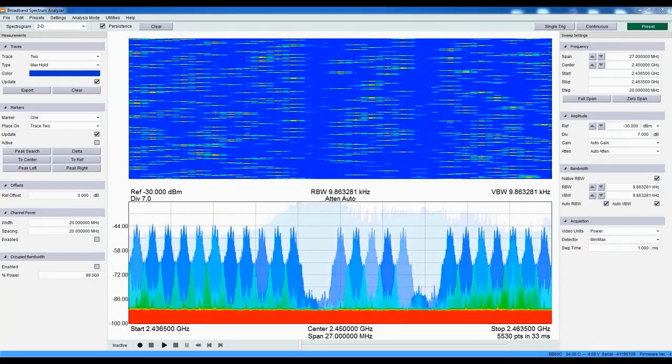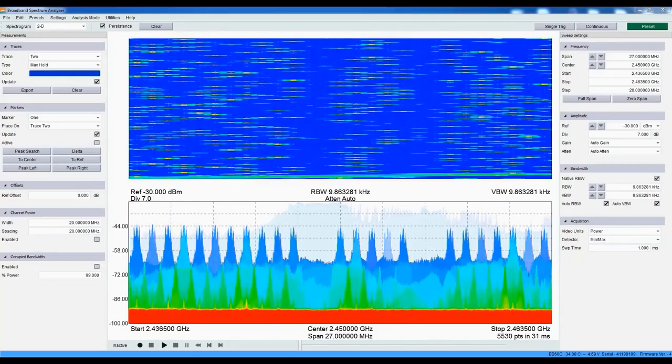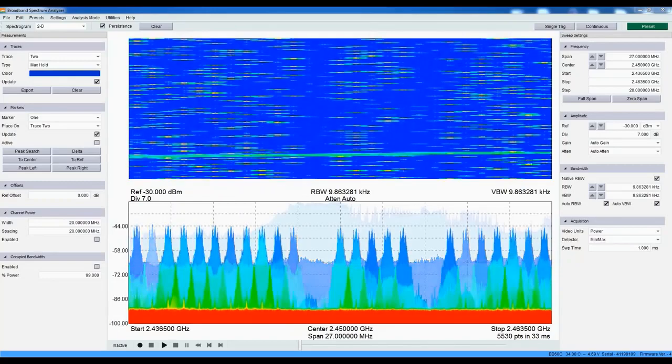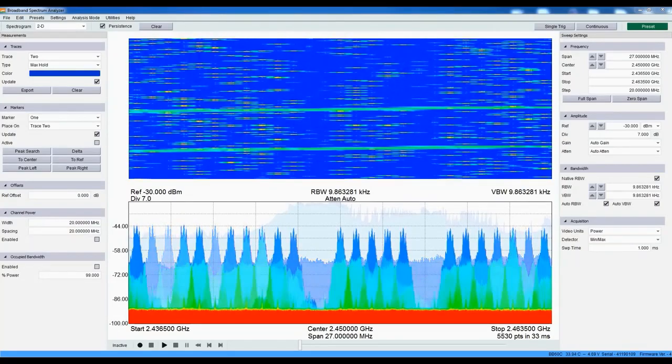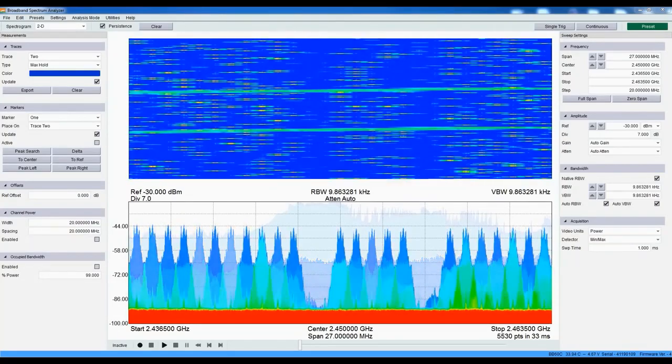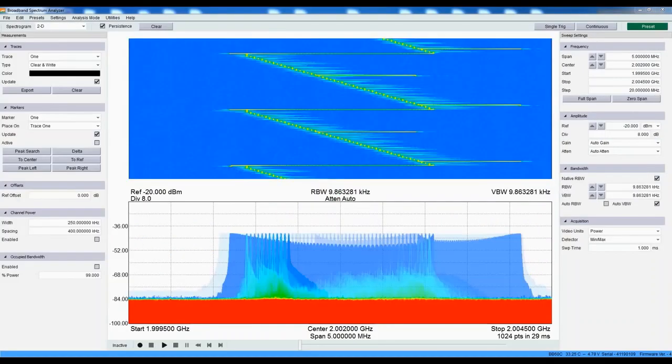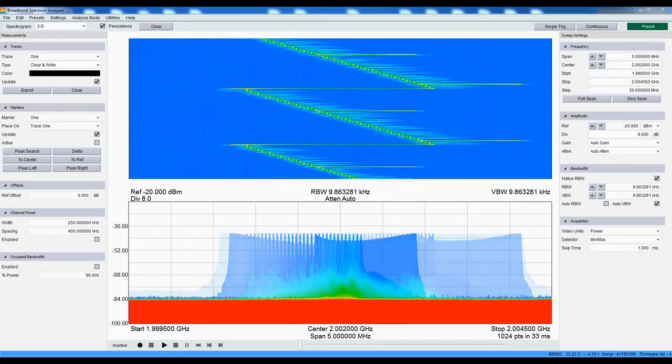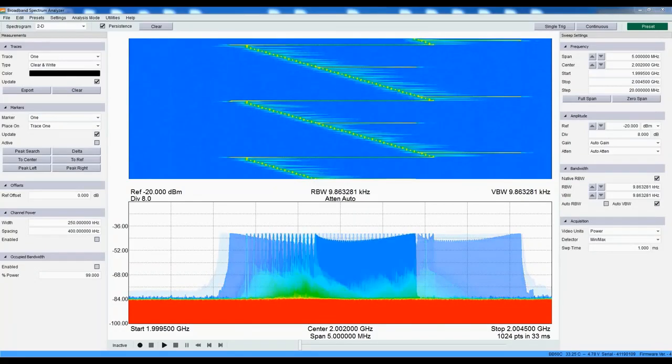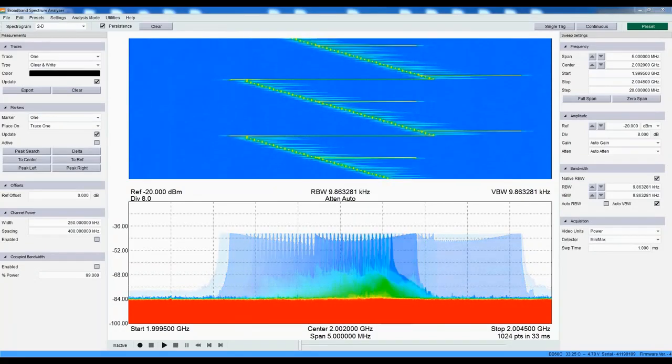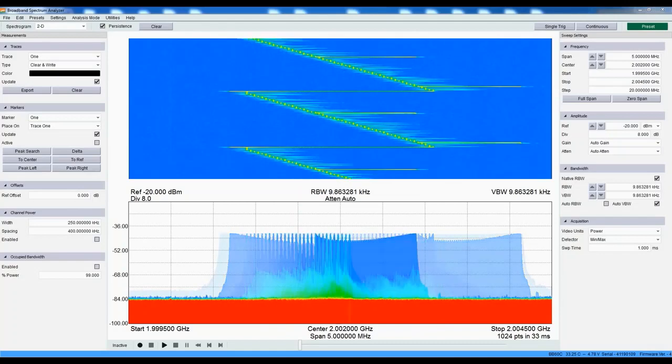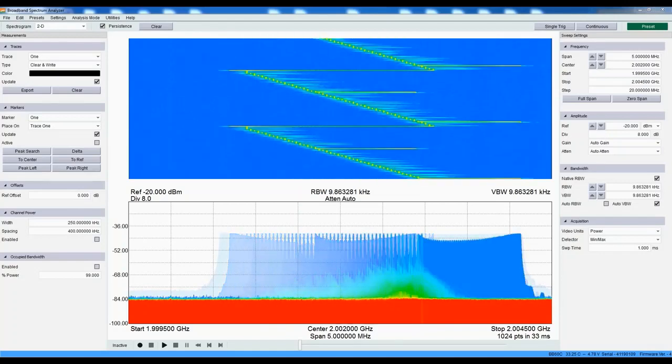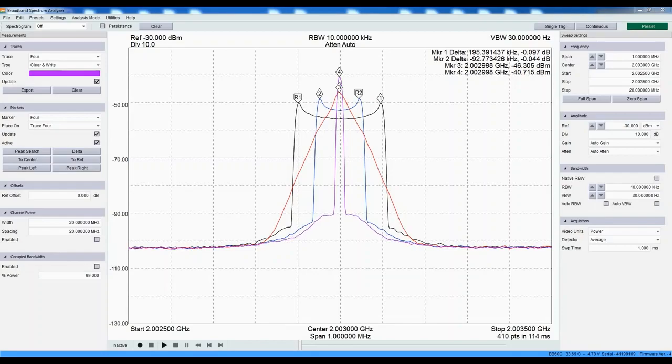Identify interfering signals and short-duration transmission bursts with the persistence and waterfall displays, and then characterize PLL overshoot and settling time using zero-span. Capture short-term spectral events such as PLL transients using real-time spectrum analysis. Add up to six traces and six markers to any configuration.